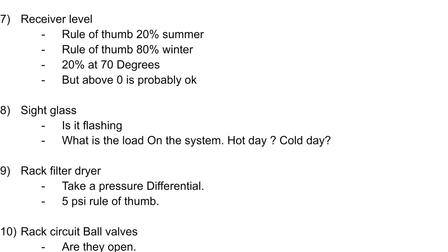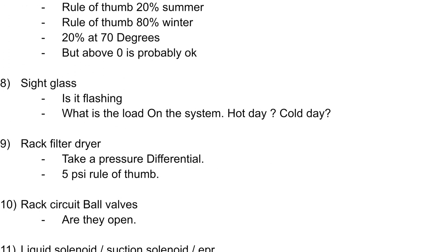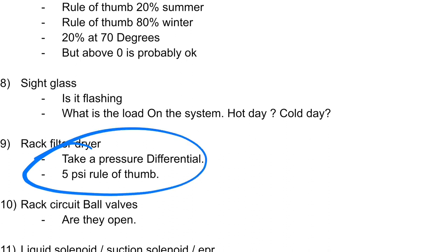which causes your receiver level to rise. Now, this isn't always the case, because sometimes your sight glass can flash on low load days or high load days. And sometimes your receiver level might be zero, but your sight glass is clear because the load is so high. So it's not a guaranteed thing, but it still could be an indicator. That's why we just check the rack filter dryer with the pressure differential.